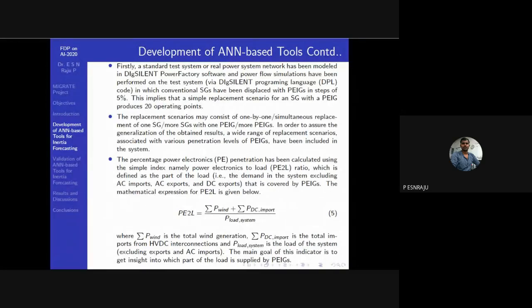For the percentage, we calculated the power electronics penetration using an index called the power electronics to load ratio. It indicates what part of the load is covered by power electronic interface generation. In the mathematical expression, the numerator has the total wind generation plus the DC import, and the denominator has the load. This indicates how much load is covered by total wind power generation plus HVDC power electronic interface lines, and that gives us the penetration level.